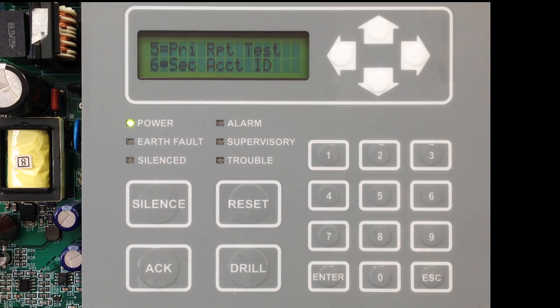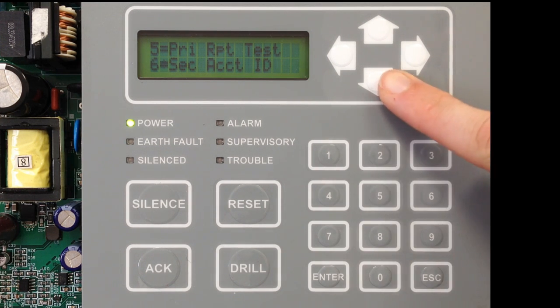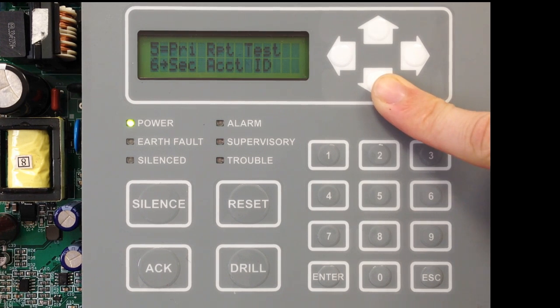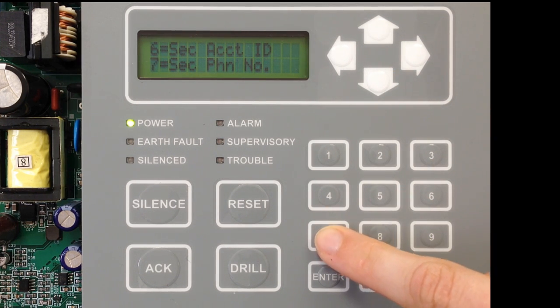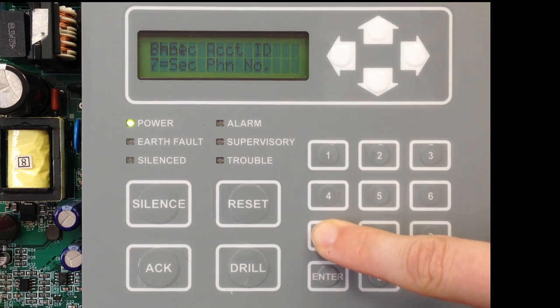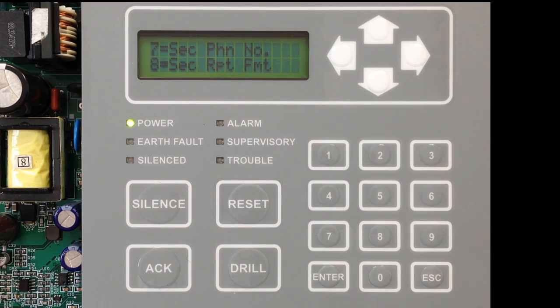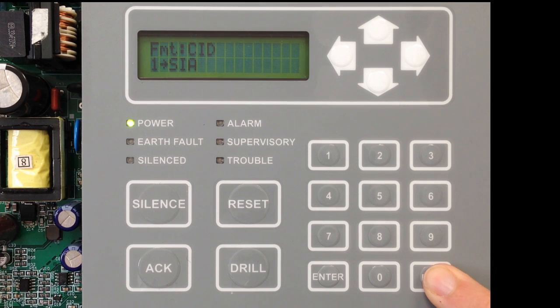Next, move to your Secondary Account ID. We've already set up the primary receiver for Account 1, and now we're setting up the backup account settings. If Central Station has given you a different account number, enter that in Secondary Account ID. If they've given you a different phone number — which they probably have — enter that in Secondary Phone Number. Then go to Reporting Format, number 8, and select SIA or Contact ID.